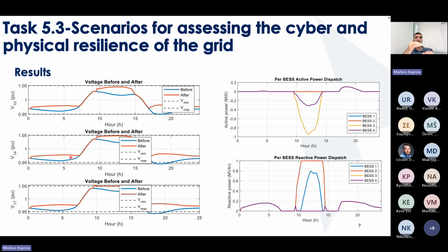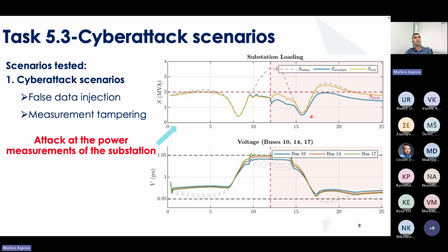But in some cases, like this one, you can see that without any control capabilities the voltage goes beyond the operational, acceptable limits. This is the response of flexible resources, such as batteries, when they charge or discharge according to the set points that the power system controllers send to them.